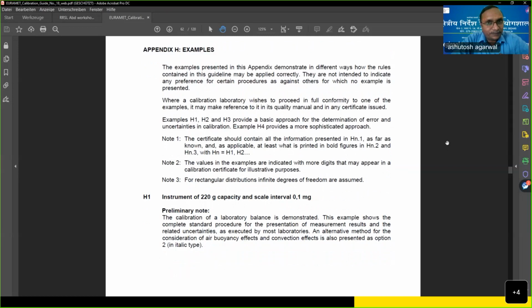Of course, I cannot define what has to be done in India, but from a strict formal metrological view, cg-18 really focuses on calibration, also, for example, on how users use the weighing instrument. If you compare the determination of the error of indication, the description says it is done the way users use a weighing instrument. They zero the balance, put something on the balance and read the indication. While in R76, you successively increase the load, which is usually not a typical weighing procedure of a user. So this guide focuses on giving the calibration result like normal user behavior.